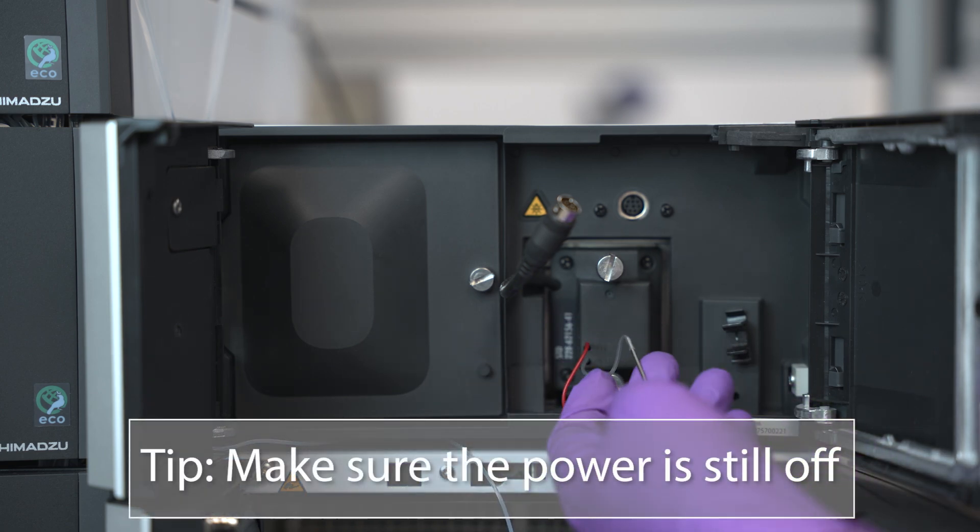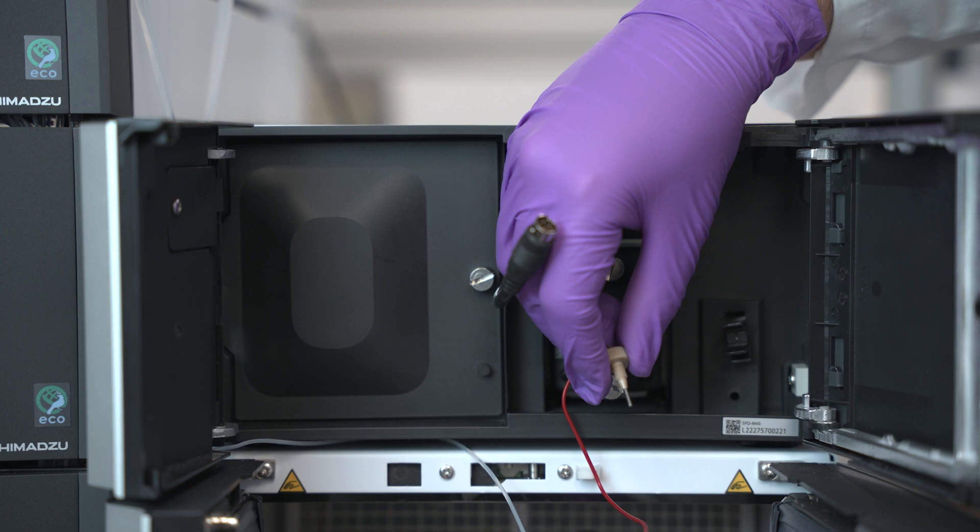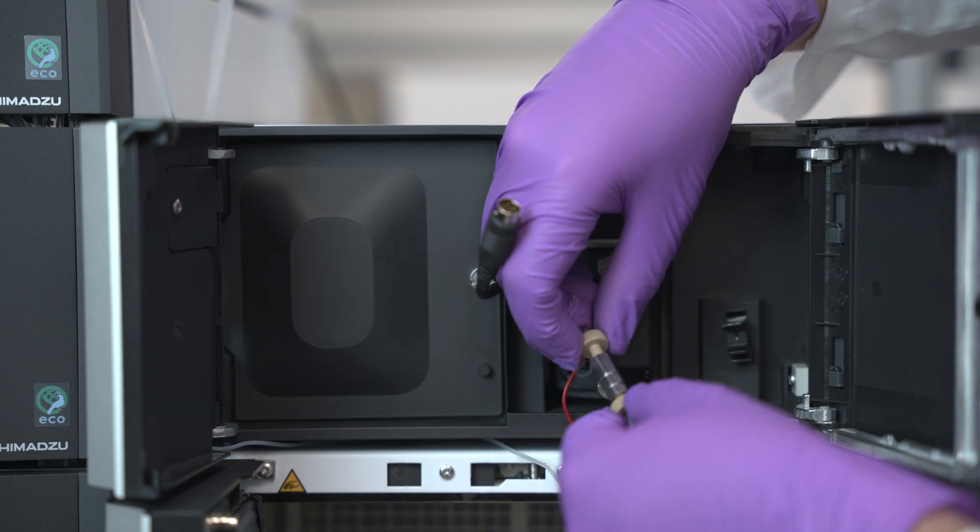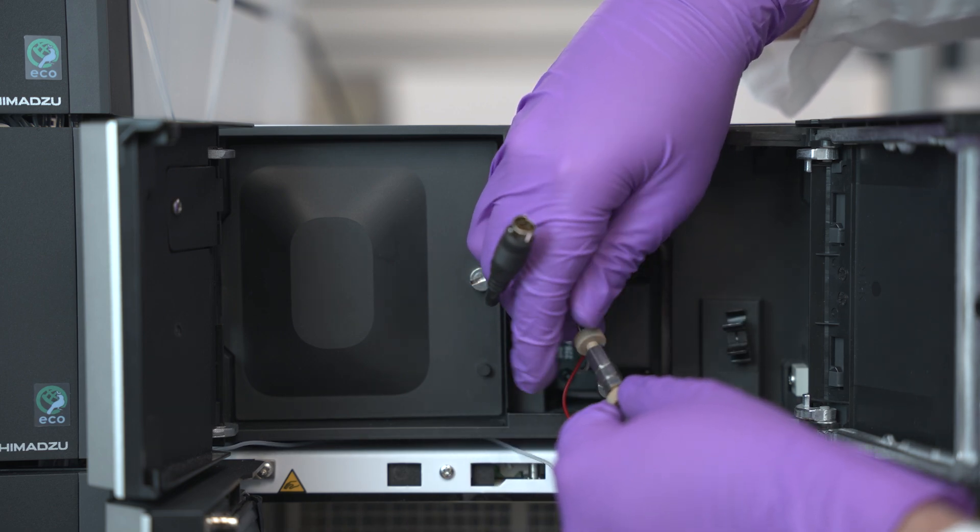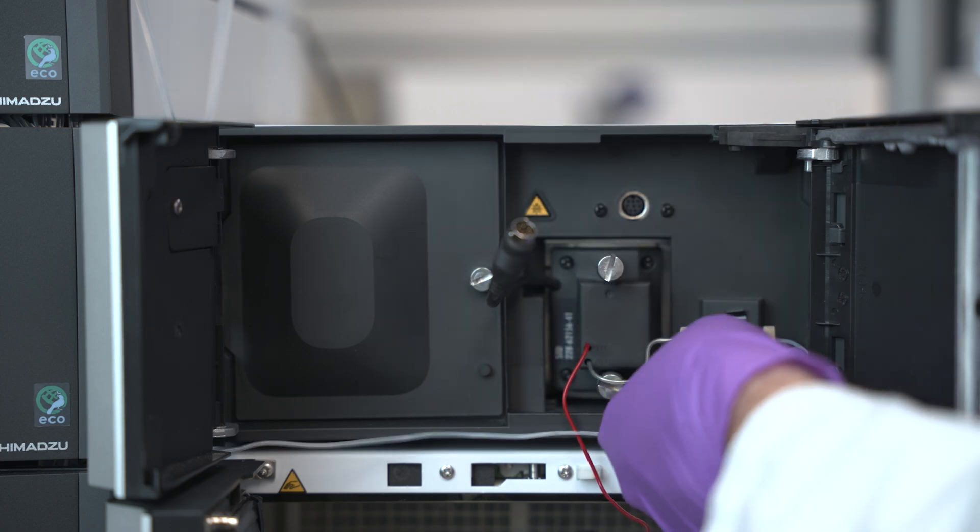Make sure the main power is still off. Attach the inlet and outlet tubing to the appropriate unions on the flow cell and fix them to the detector with the coupling holder.